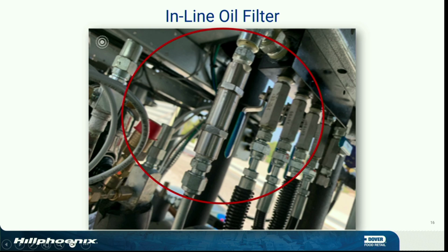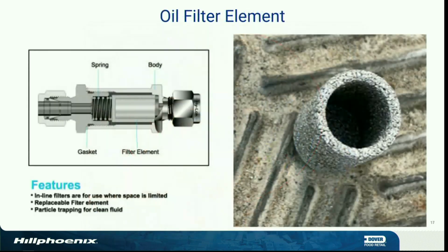All right, these are in-line. Again, like I said, these are the 8mm size ones. They are small because this is an 8mm line. Guys, if you don't know, it's a very small line. It's like 5/16. Again, this is the little porous rock on the inside of the filter. You can take it apart and clean it and put it back together. Make sure you put it back together the same way you took it out. Pay attention when you're pulling it apart because you want to be on the outside. If you put it in backwards and it goes just through the center, you don't have as much surface area, okay?